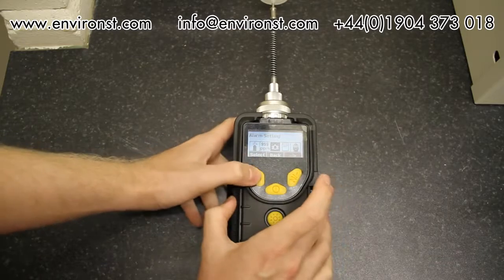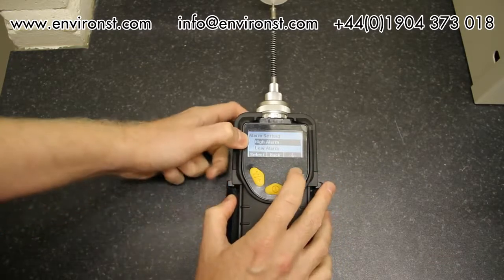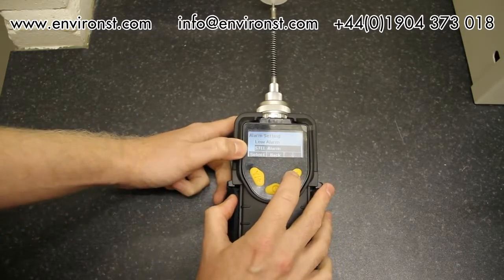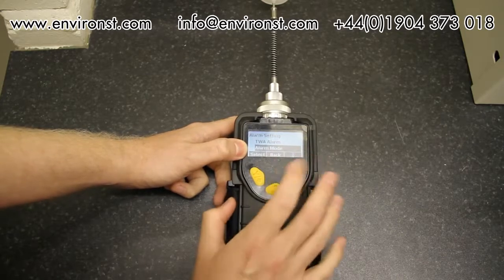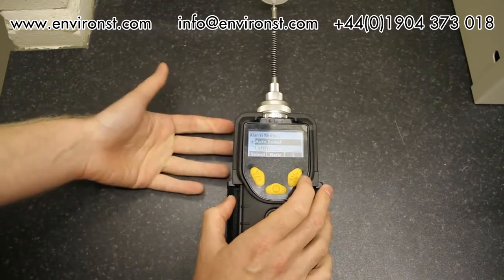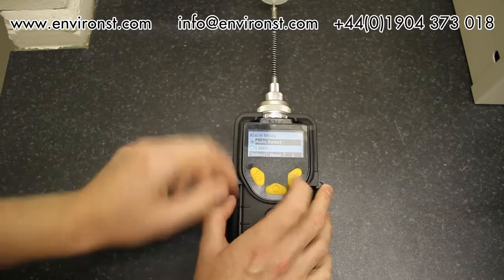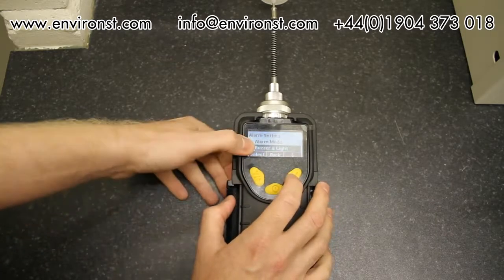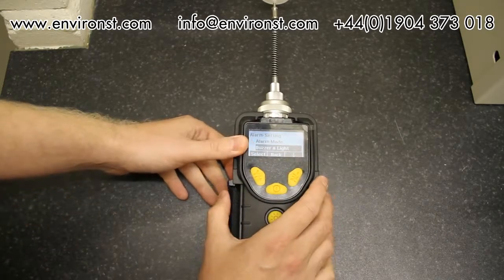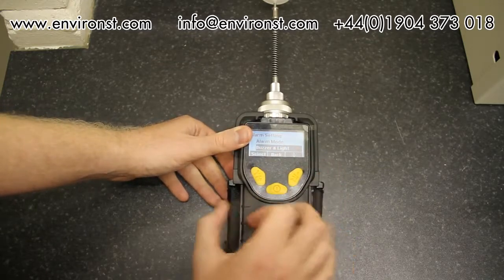So we go across to alarms. Now this is where I can change the high alarm, the low alarm, STEL alarm, TWA alarm, and I can change the alarm mode. So if I want to change the alarm mode, I can put it into auto reset or latching. And you can set what you want to come on in the alarm. So you've got buzzer and lights.